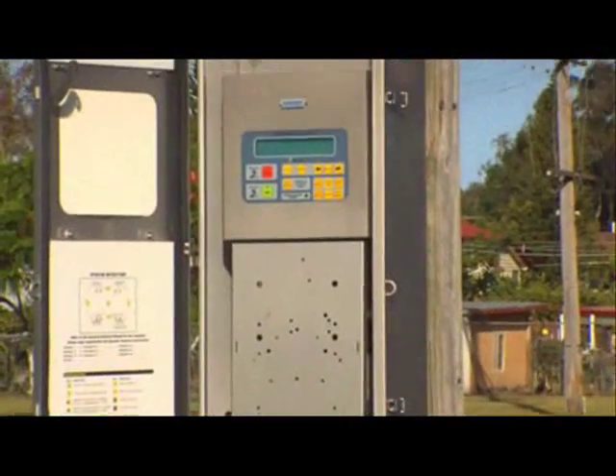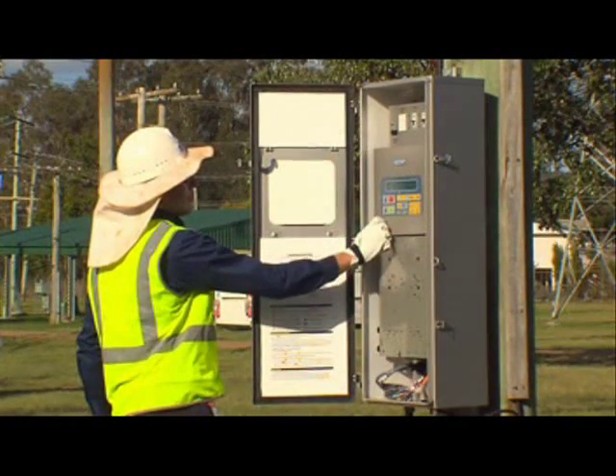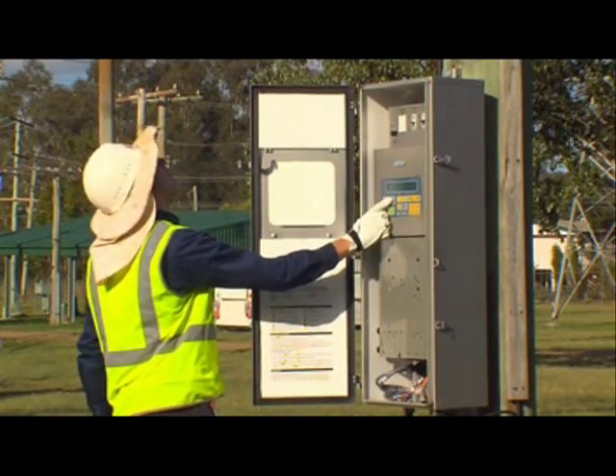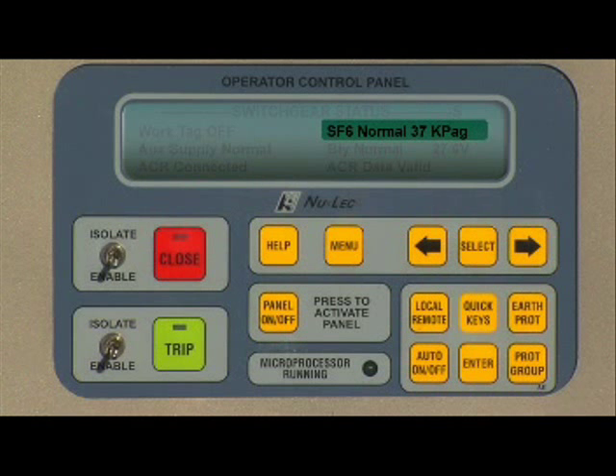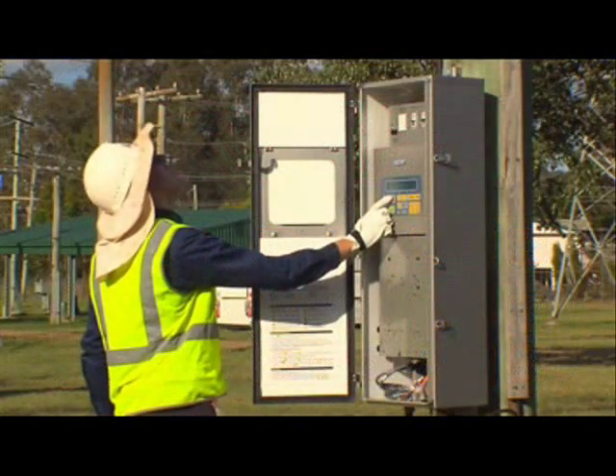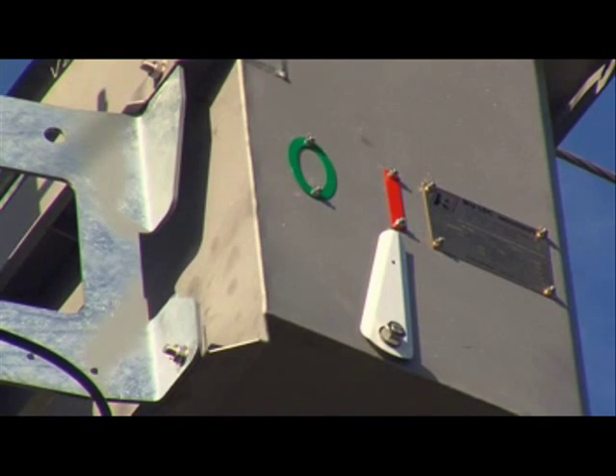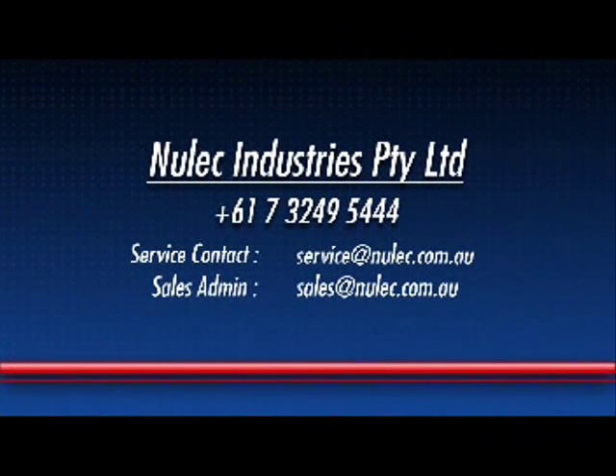Once the control cable and earth connections have been completed, the controller can be powered up by switching on both MCBs. A quick diagnostic test can be completed by cycling to the switchgear status screen on the front panel. For normal operation, this screen should read: SF6 pressure 37 kilopascals, auxiliary supply normal, battery voltage 27 volts, ACR connected, ACR data valid. If all these status points are satisfied, the switchgear can be successfully operated. If there are complications with your installation, please refer to the N-Series technical manual or contact Nulec Industries directly for any further questions.